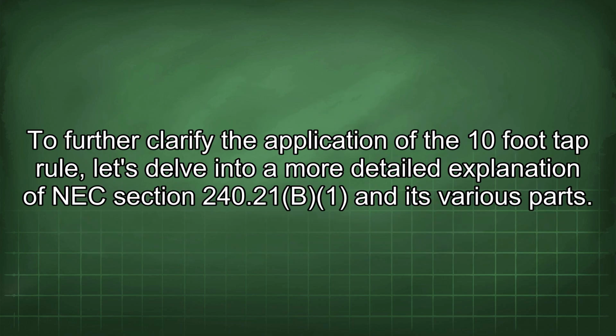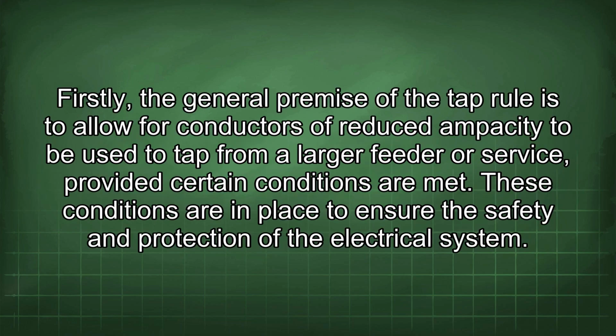To further clarify the application of the 10-foot tap rule, let's delve into a more detailed explanation of NEC Section 240.21(B) and its various parts. Firstly, the general premise of the tap rule is to allow for conductors of reduced ampacity to be used to tap from a larger feeder or service, provided certain conditions are met. These conditions are in place to ensure the safety and protection of the electrical system.